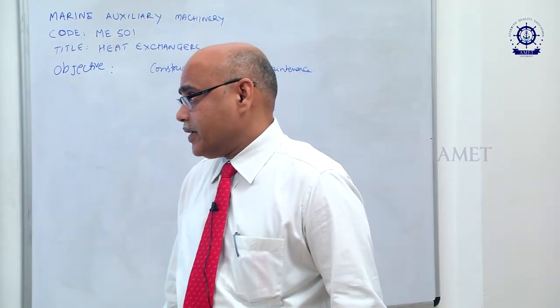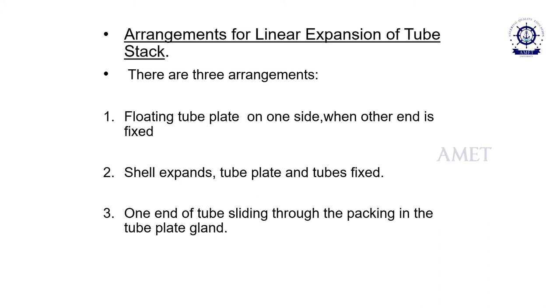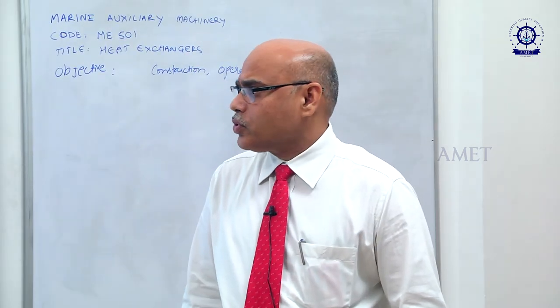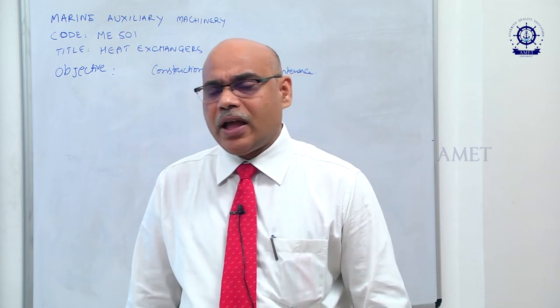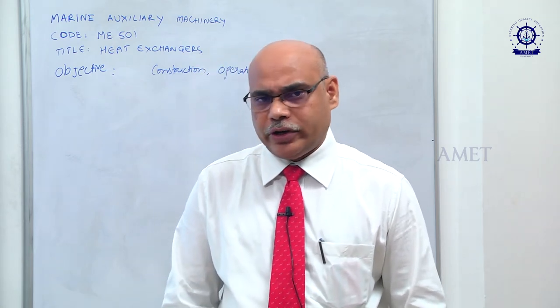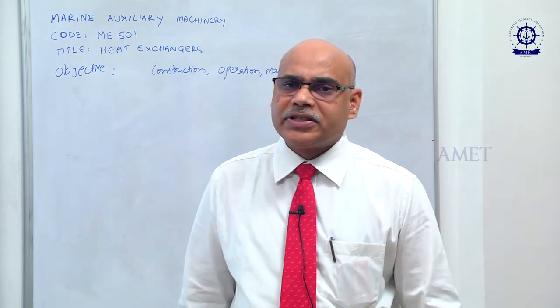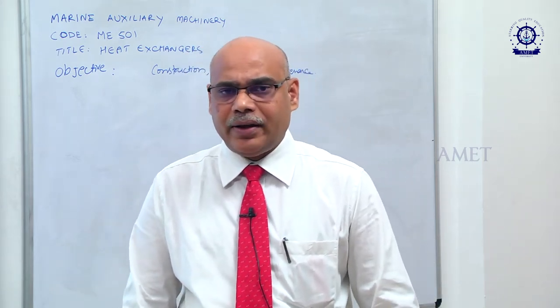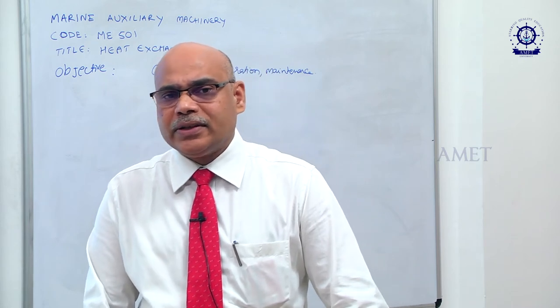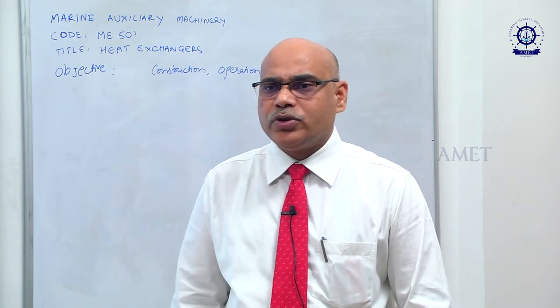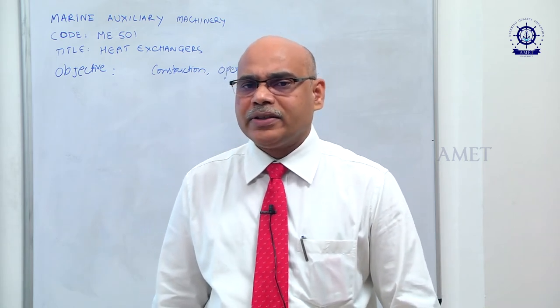Arrangements for linear expansion of the tube stack — there are three methods. One is that one end of the tube is fixed and the other end is freely floated. The second method is that both tube end plates are fixed but the shell is allowed to expand. The third method is one side of the tubes is fixed and the other side the tubes can expand in a stuffing box.